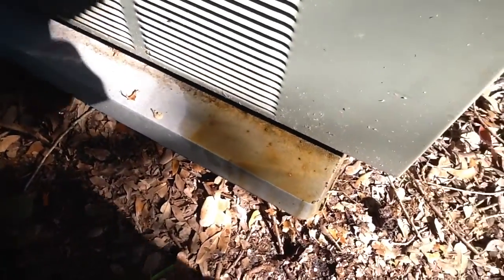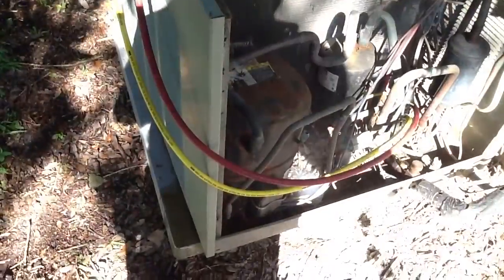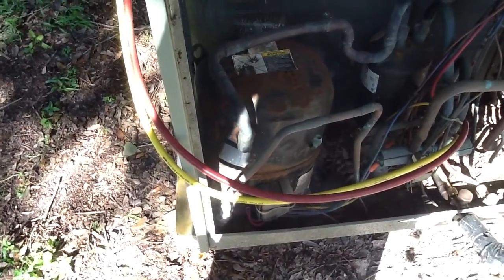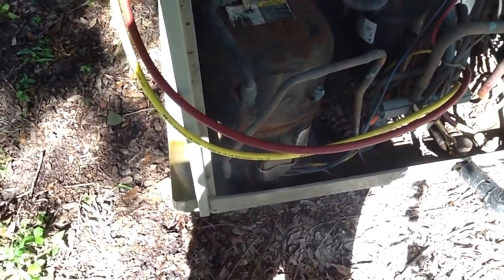This compressor — looks like all the oil, the oil from the compressor — oh yeah, this is definitely the oil from the compressor. This is something you normally don't see on a daily basis. It's the first time I've seen this. It's literally leaking from underneath, and that is all the oil from the reciprocating compressor. She's a leaker underneath and she's super hot.